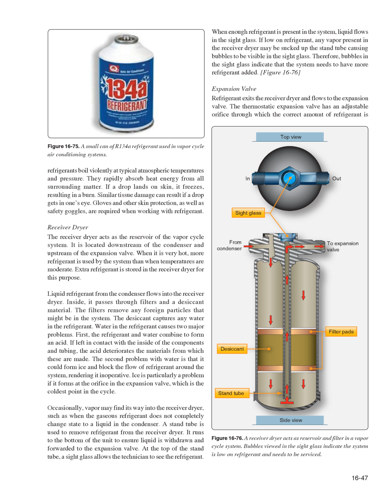Water in the refrigerant causes two major problems. First, the refrigerant and water combine to form an acid. If left in contact with the inside of the components and tubing, the acid deteriorates the materials from which these are made. The second problem with water is that it could form ice and block the flow of refrigerant around the system, rendering it inoperative. Ice is particularly a problem if it forms at the orifice in the expansion valve, which is the coldest point in the cycle. Occasionally, vapor may find its way into the receiver dryer, such as when the gaseous refrigerant does not completely change state to a liquid in the condenser. A stand tube is used to remove refrigerant from the receiver dryer. It runs to the bottom of the unit to ensure liquid is withdrawn and forwarded to the expansion valve. At the top of the stand tube, a sight glass allows the technician to see the refrigerant.